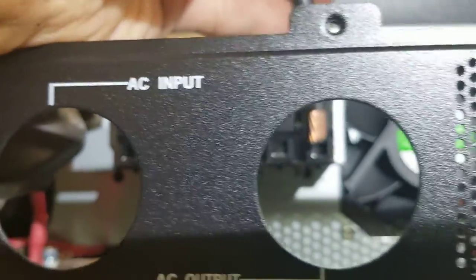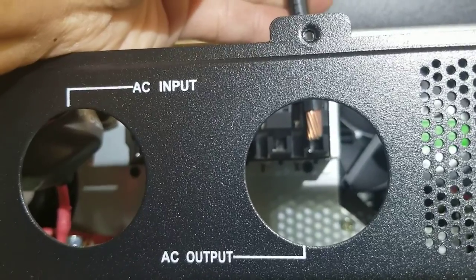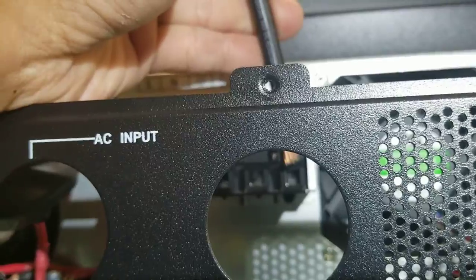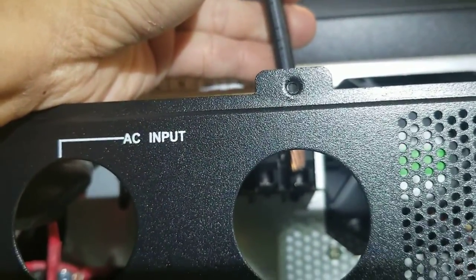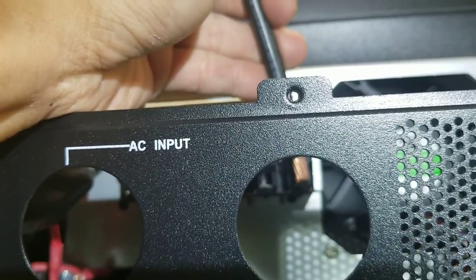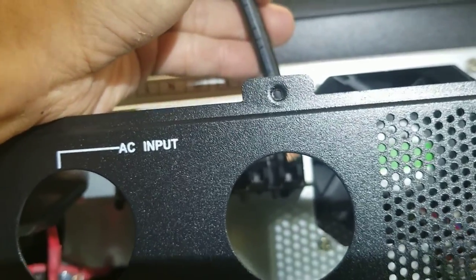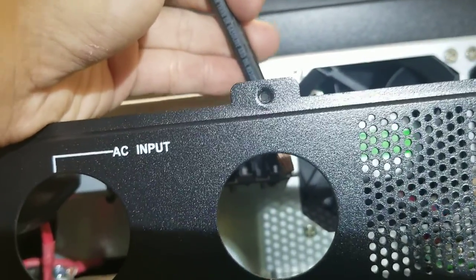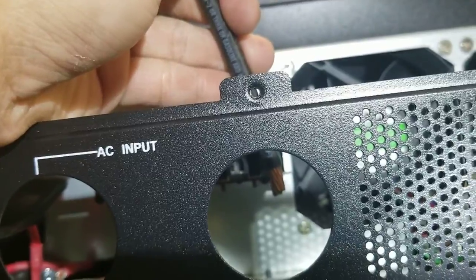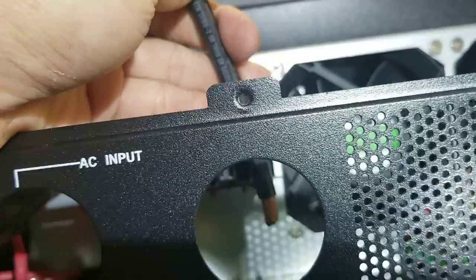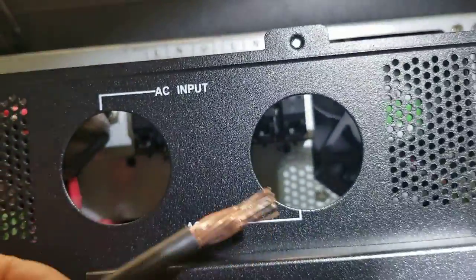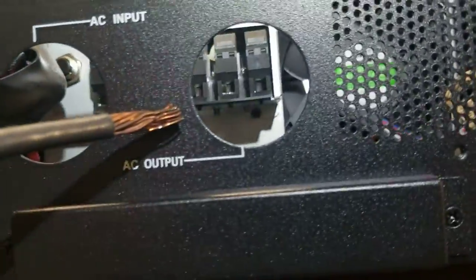They suggest, rather than recommend, to have a 4 gauge wire for the 6,500 watts. If you calculate 6,500 watts divided by 120 volts, it comes out to about 54 point something amps. If you look online or at a department store, you'll see the 4 gauge is rated up to 95 amps, and the 6 gauge is already 75 amps. So why do they suggest you put in a 4 gauge here?